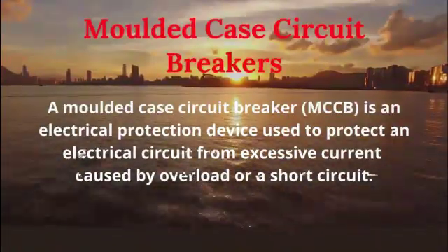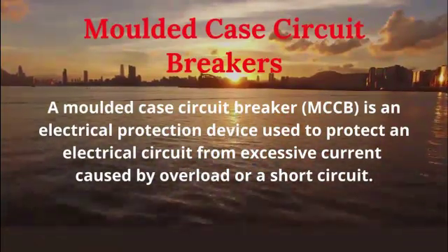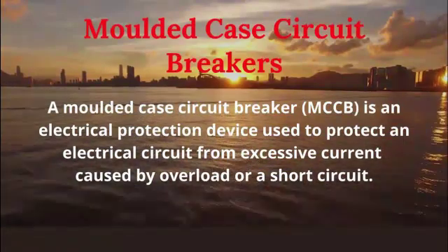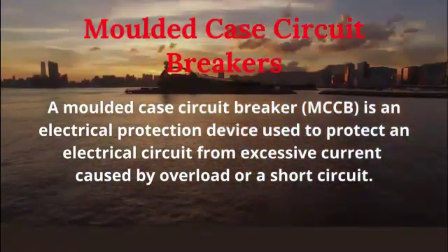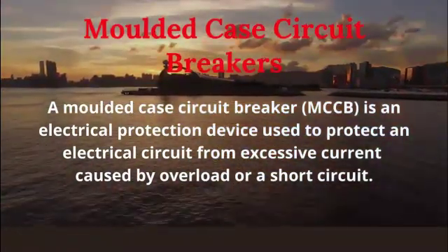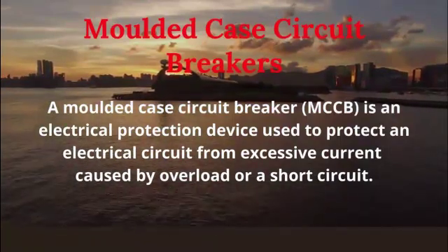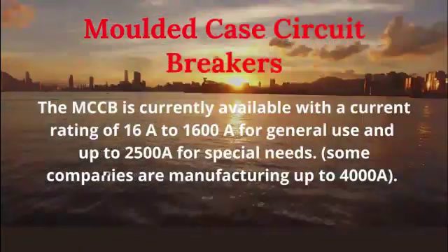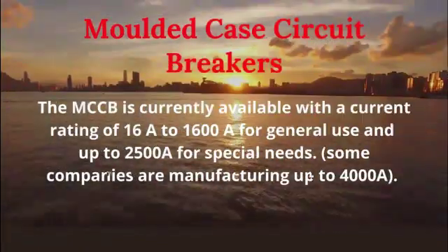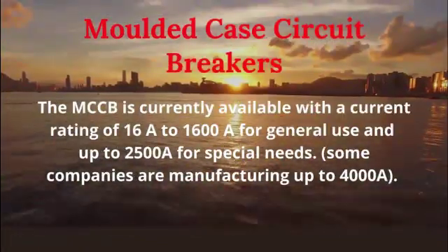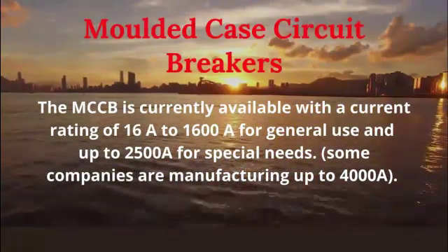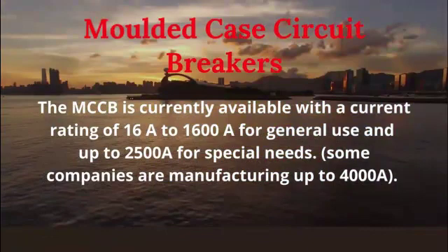A molded case circuit breaker is an electrical protection device used to protect an electrical circuit from excessive current caused by overload or a short circuit. The MCCB is currently available with a current rating of 16A to 1600A for general use and up to 2500A for special needs.